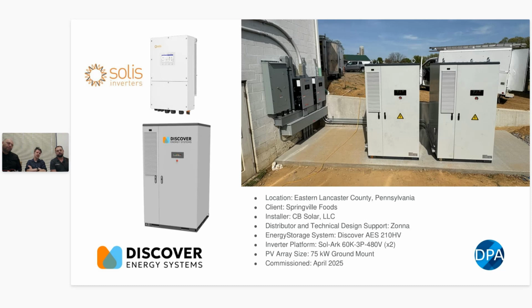The nice thing too - though you can't see it in this example since they brought all the DC, AC, and comms connections through the side of the cabinet - is that if you have the foresight to pre-pour your concrete pad and run conduit up, you can install it coming through the bottom. There's also zero space requirement between the cabinets, so you can sandwich them together to minimize overall space required. That's a bigger issue in the States, the space between cabinets. You don't need to with this cabinet at all.